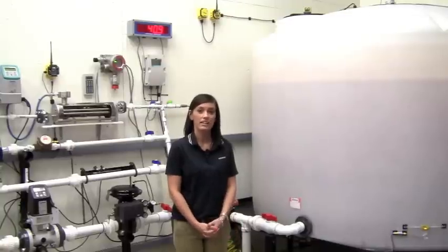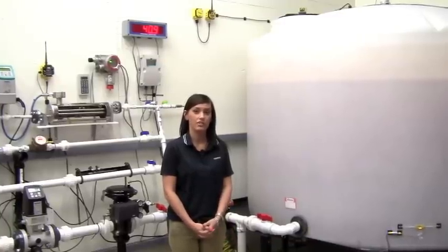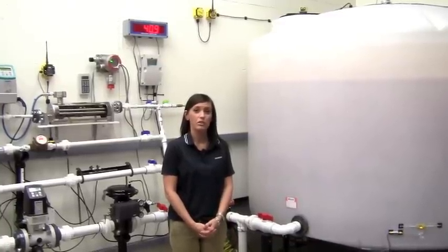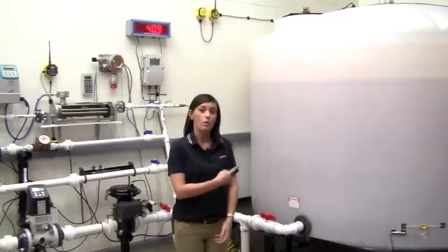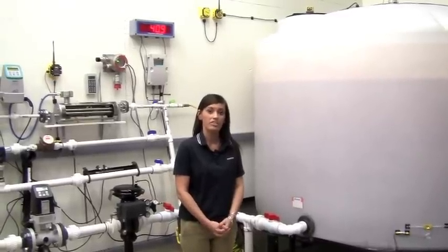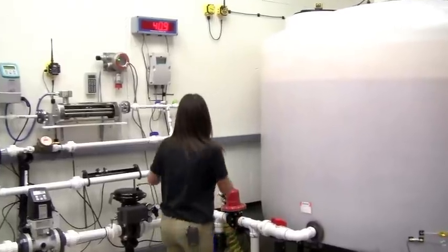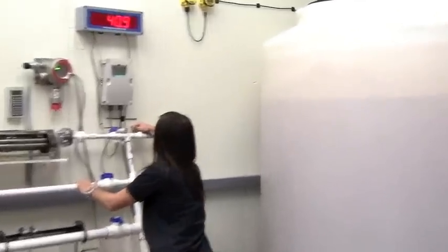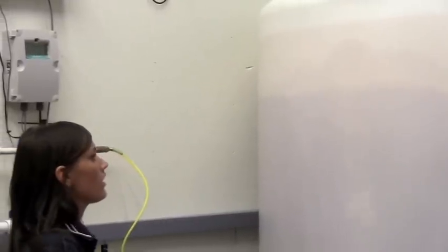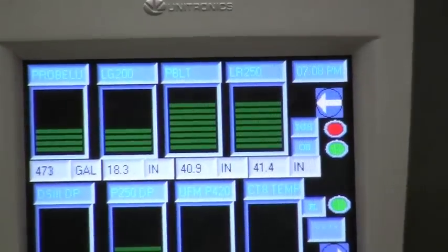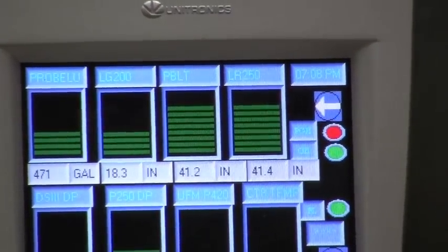In the past, you may have had issues with a turbulent or agitated surface. The LR250 will erase these issues. What we're going to do here is simulate that by putting aeration into the tank. You can see the tank filling with air. Now let's take a look at the display to see a steady reading. You can see the agitated surface has little to no effect.